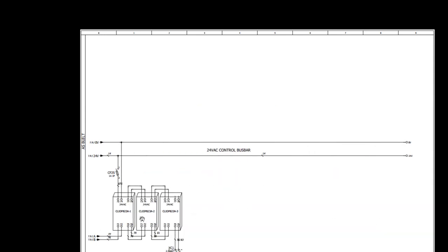These are all digital input modules, CLIOP 8231. These have only 12 digital input points. Then this cable from the last module is going to terminal XC134. Why is this going there? If there is another slave panel, we can connect that panel in the same loop, so that it will be communicating over the same channel. So it is optional, and if it is required it will be used. Otherwise, if you have only one panel, it will not be used, or these terminals will not be there.